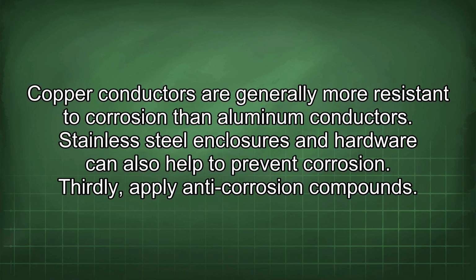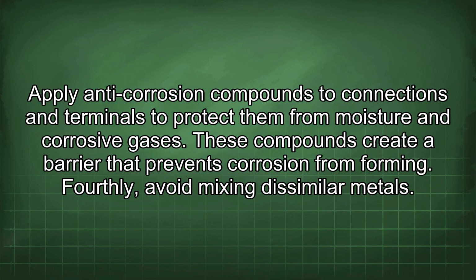Stainless steel enclosures and hardware can also help to prevent corrosion. Thirdly, apply anti-corrosion compounds. Apply anti-corrosion compounds to connections and terminals to protect them from moisture and corrosive gases. These compounds create a barrier that prevents corrosion from forming.